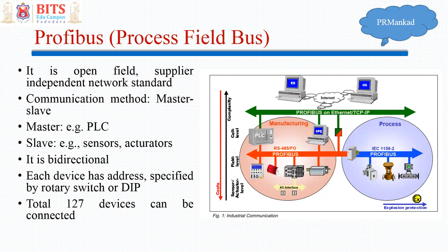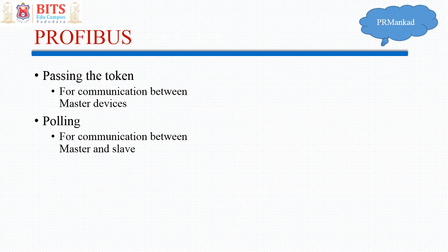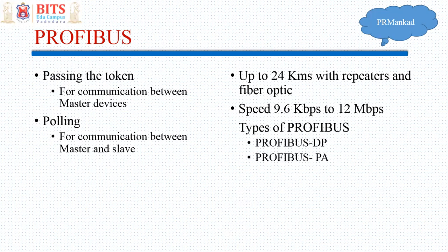Communication between masters takes place by token passing — a token is passed between masters, and whichever master holds the token and signals readiness sends the request, then the slave responds with data. Profibus features include coverage of up to 24 kilometers with repeaters and fiber optic. Speed varies from 9.6 kbps to 12 Mbps — shorter distances support higher data transfer speeds. There are two types: Profibus DP and Profibus PA.